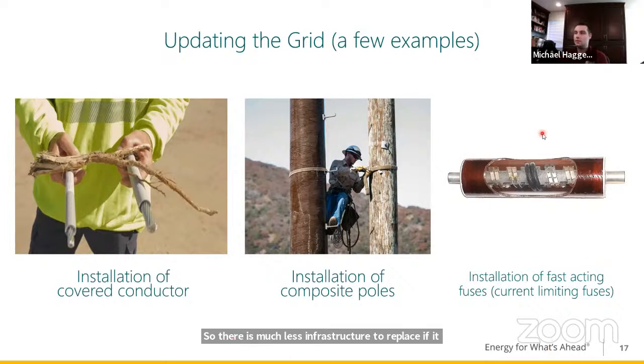And lastly, what's been distributed in mass across all the circuits that traverse high fire risk areas is the installation of fast acting fuses, called current limiting fuses. You can see a cross section of one here - these shiny metal components are the current limiting components, and then there's the more traditional fuse components in the middle that work for lower amperage faults.